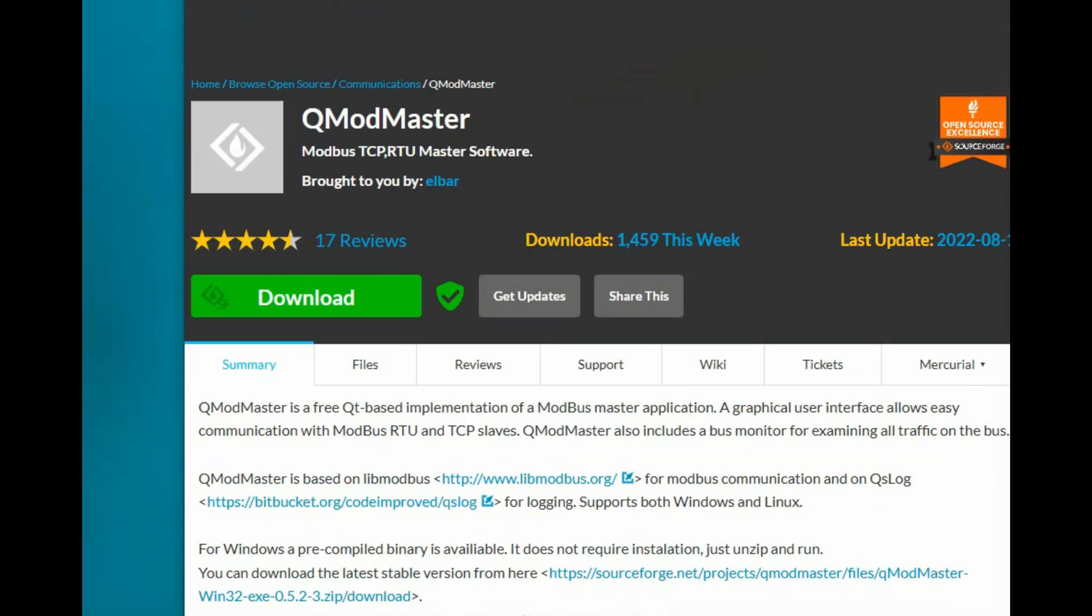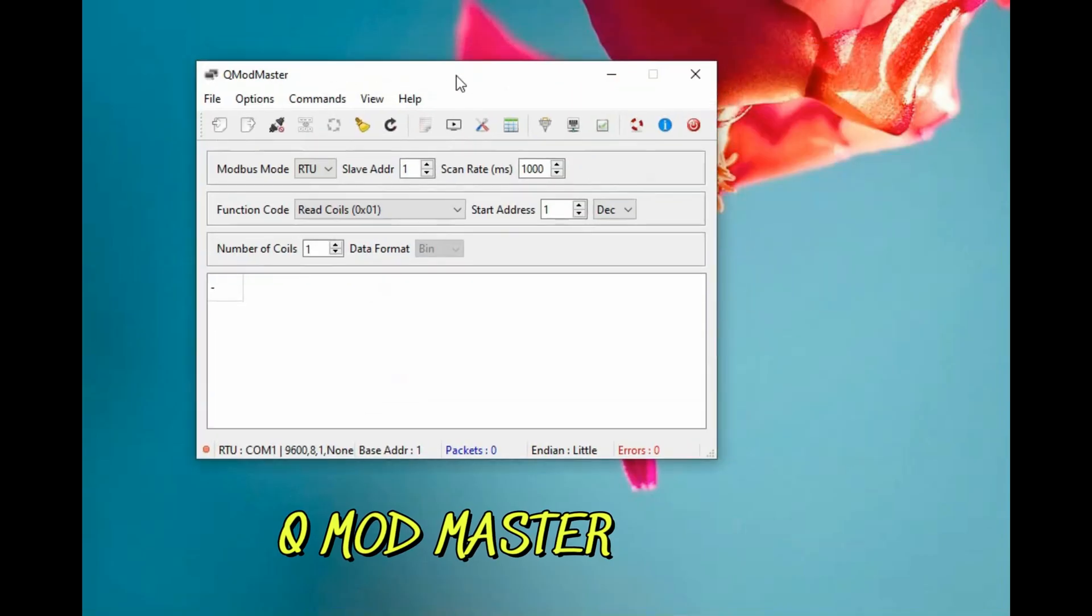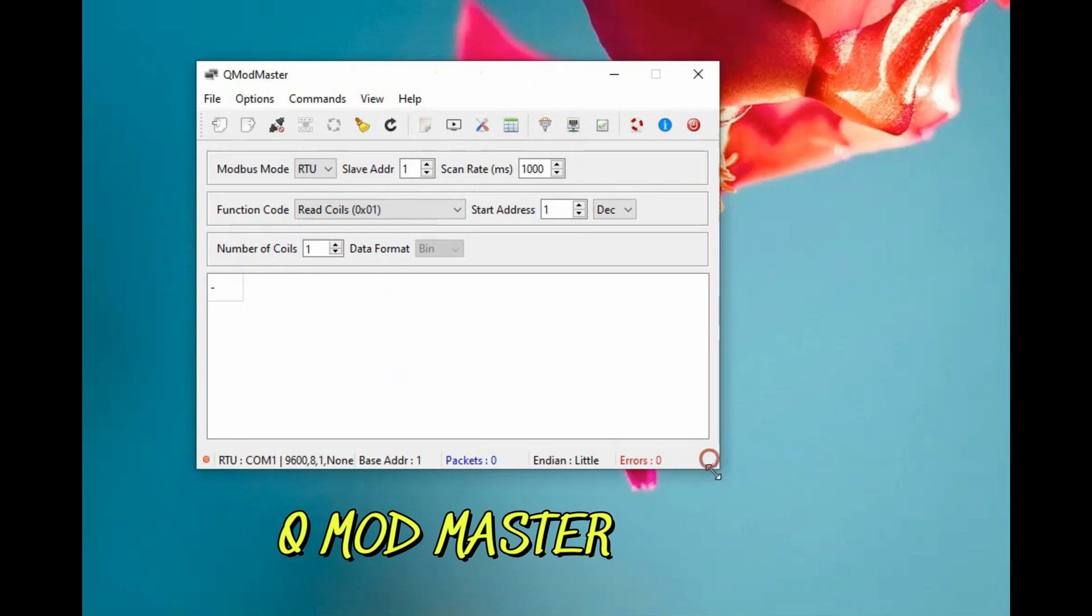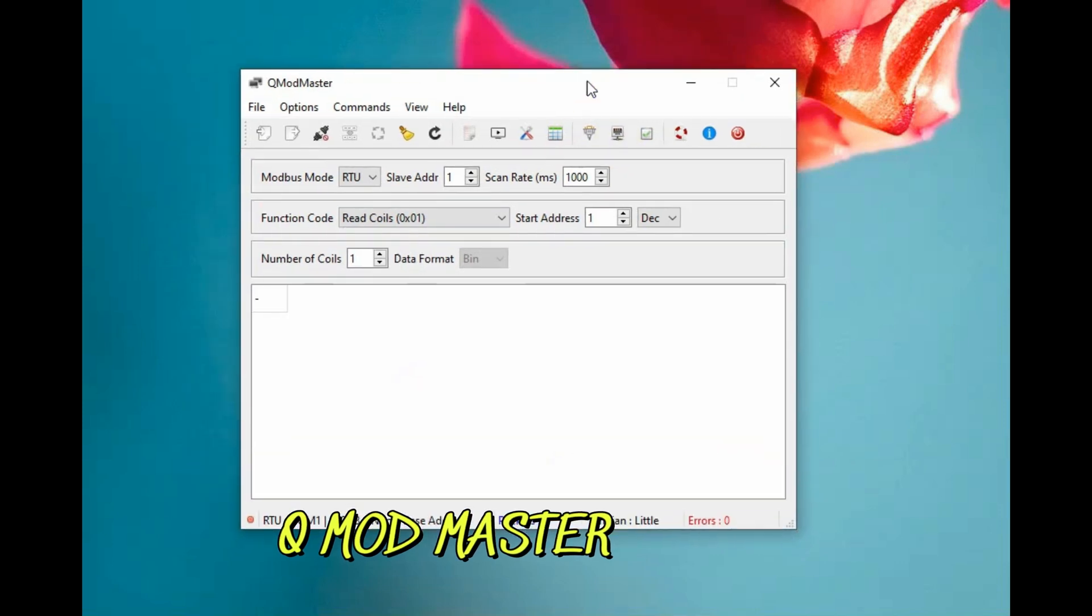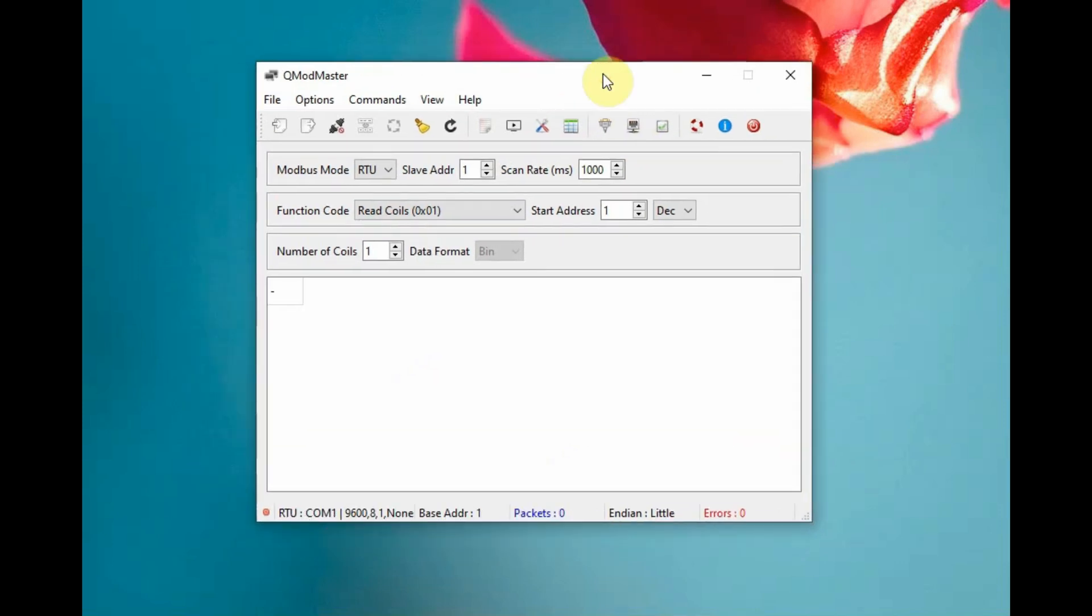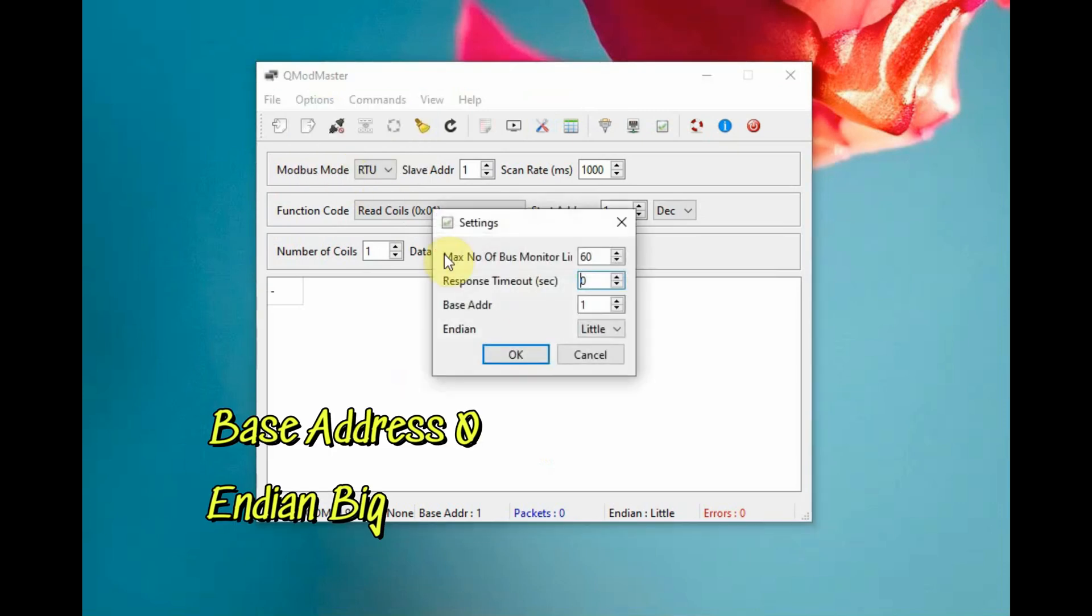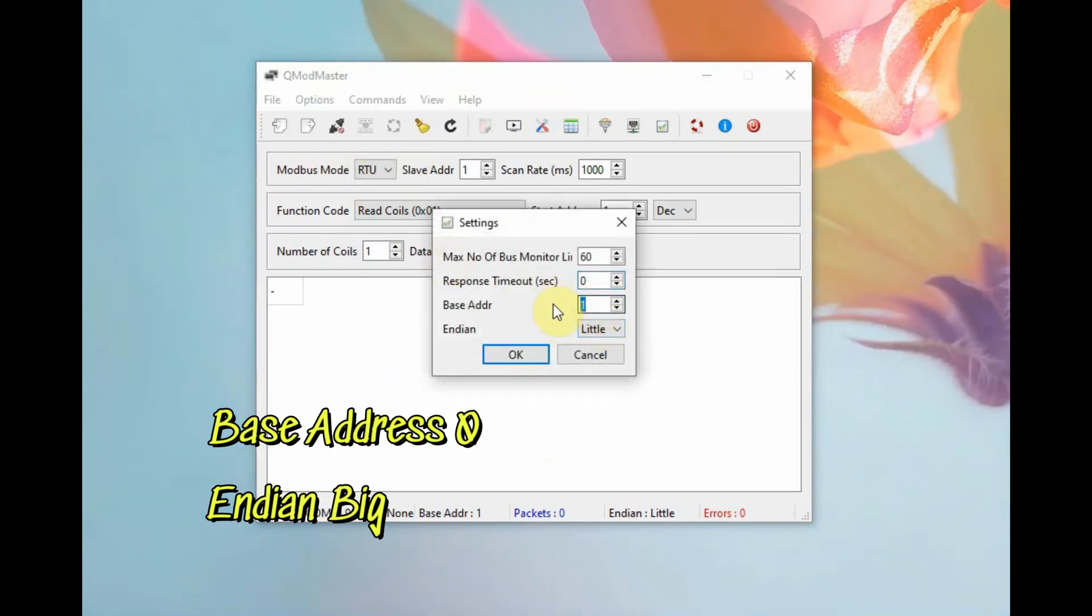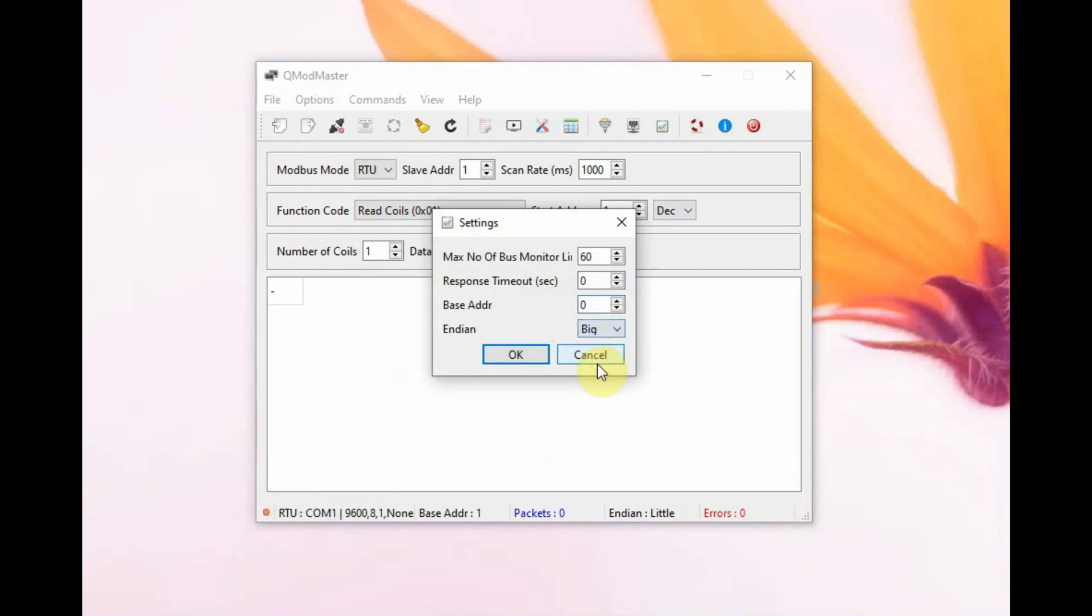Open the software and in settings, use the base address as 0 and the endian as big endian, that is high byte first. Under Modbus RTU settings, note the COM port allotted to the RS485 to USB.